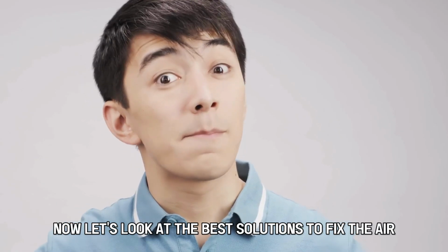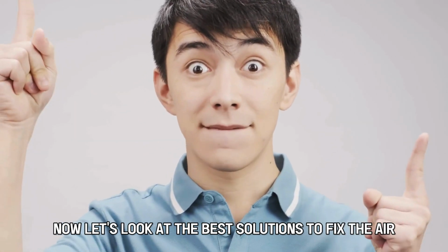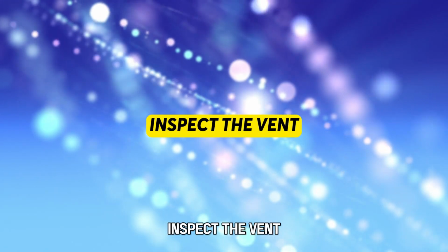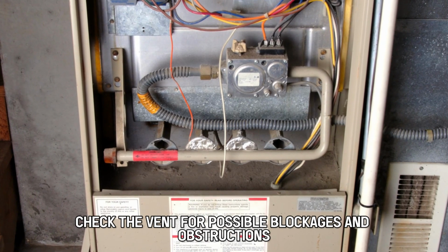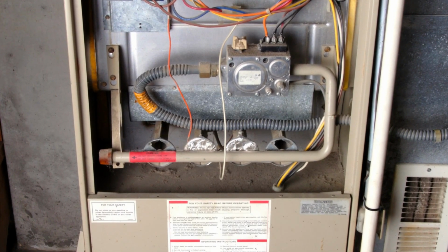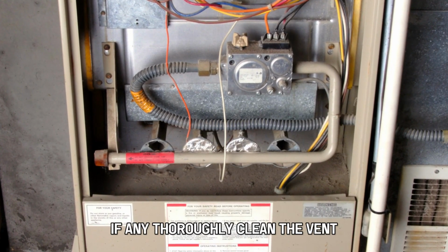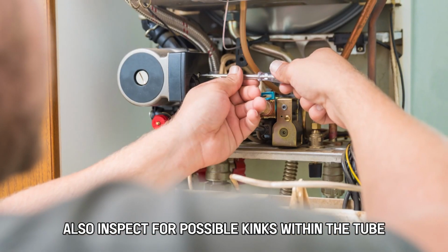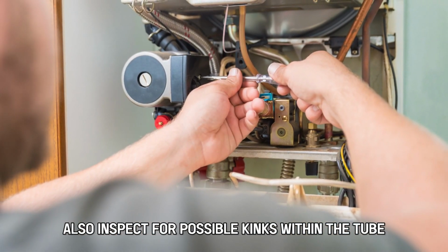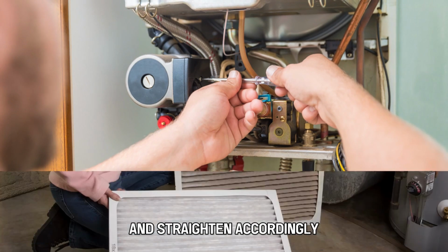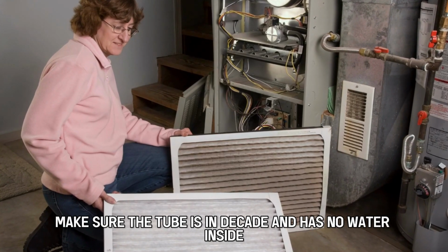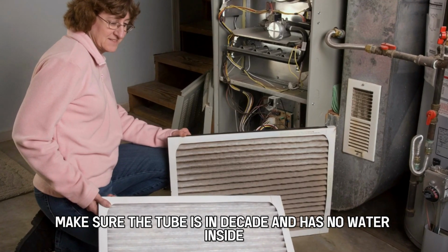Now let's look at the best solutions to fix the error. Inspect the vent: check it for possible blockages and obstructions, and if any, thoroughly clean the vent. Also inspect for possible kinks within the tube and straighten accordingly. Make sure the tube isn't decayed and has no water inside.